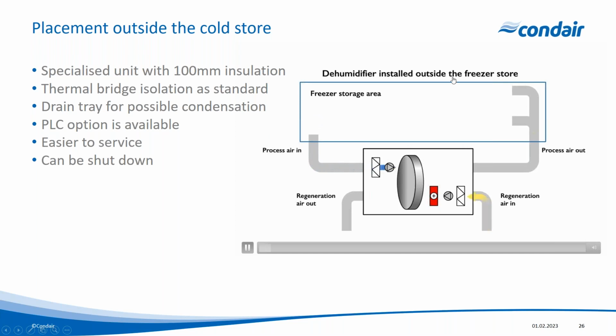Again, if we look on the right-hand side here, and we imagine that this blue area is our freezer store, we could mount the dehumidifier outside of the freezer store. We could take our process air from the freezer store into our dehumidifier through a filter and a fan, and we capture the moisture, and then we send that dry air back into the freezer store. And our regeneration air is coming from ambient, going back into the dehumidifier over a filter and a fan, over the heater, and drying out the rotor, and then being sent outside.